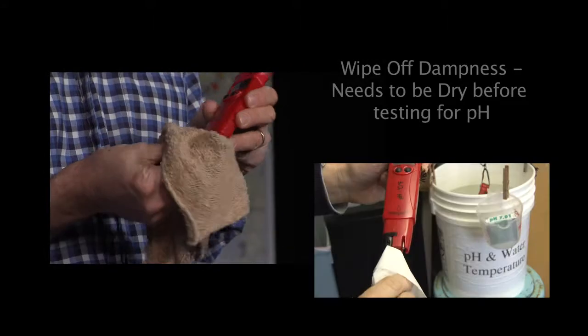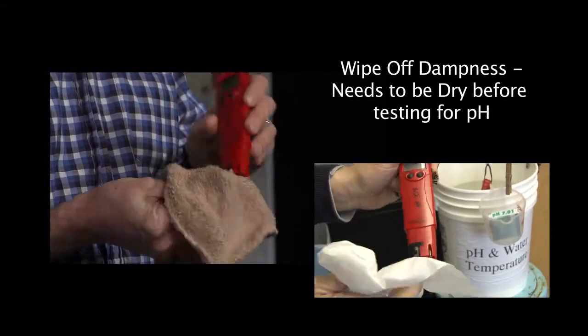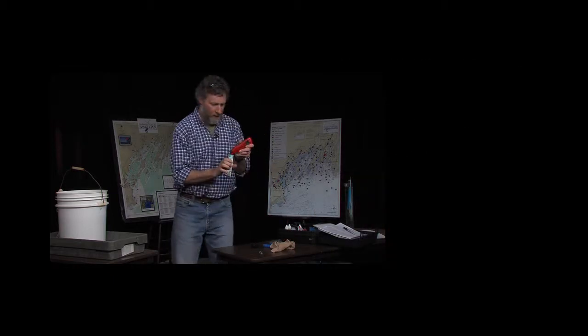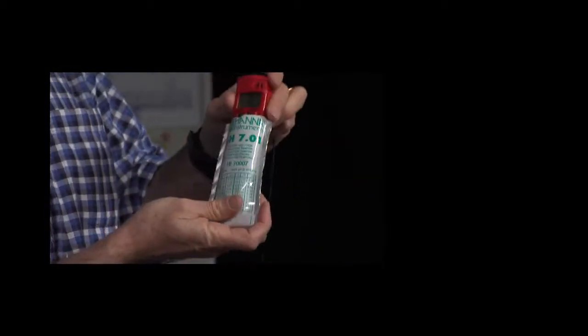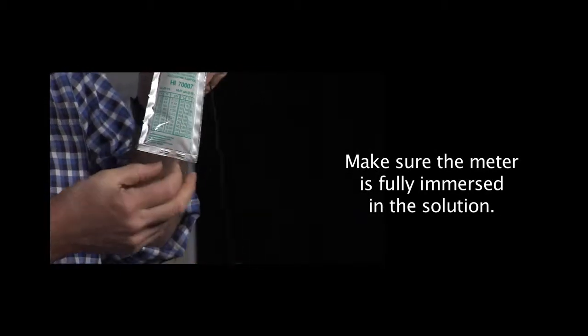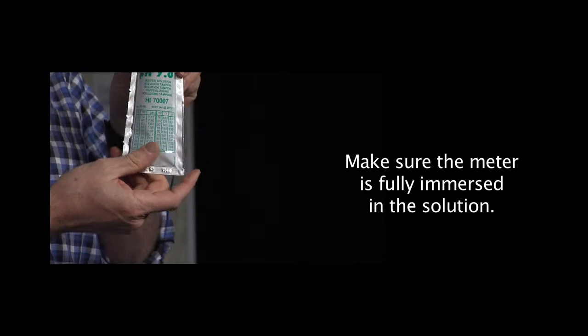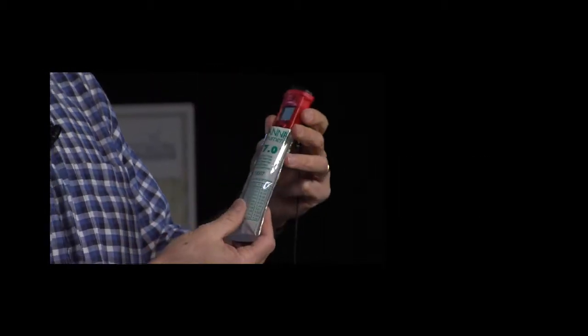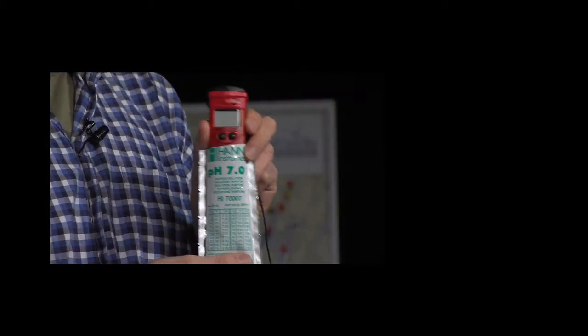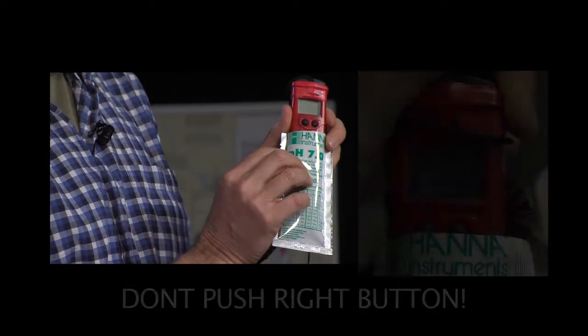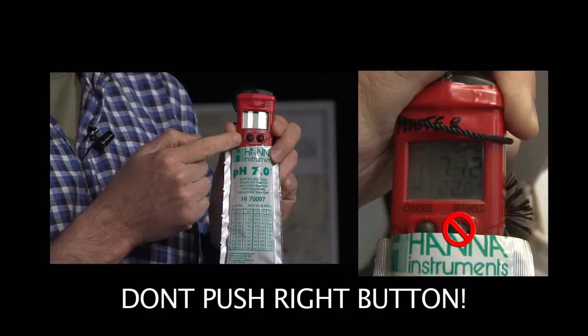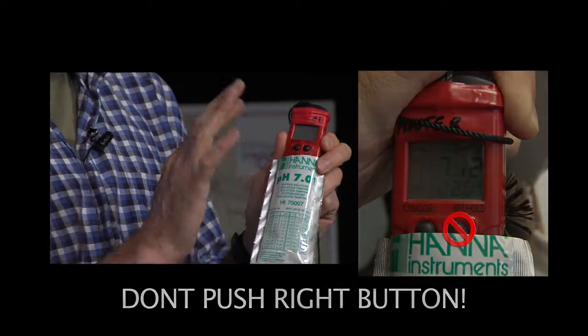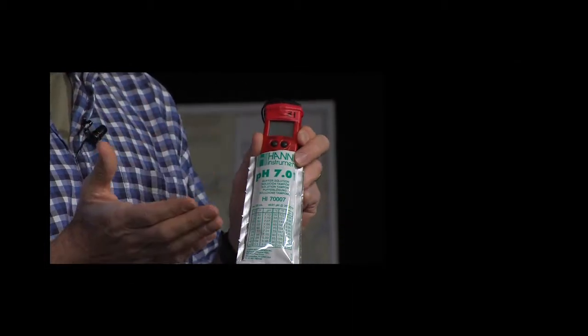So that we don't contaminate our calibration solution, I'm going to take a little towel and wipe off whatever dampness there is on the probe, and we'll put the meter down in the packet. There's a little bit of fluid in there that is a known pH of 7.01, and shake it around a little bit. And we're going to turn the meter on by pushing the left button. When you go to do the calibration and when you're going to use the pH meter, the only button on the face of this meter that you're going to want to use is the one on the left. You can ignore the one on the right-hand side. That actually changes the temperature thermistor from Fahrenheit to Celsius.